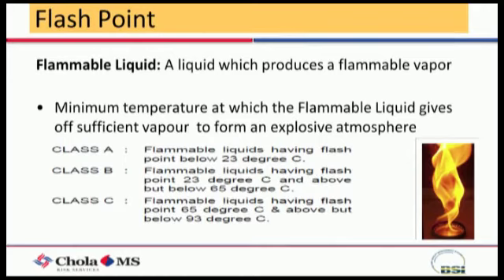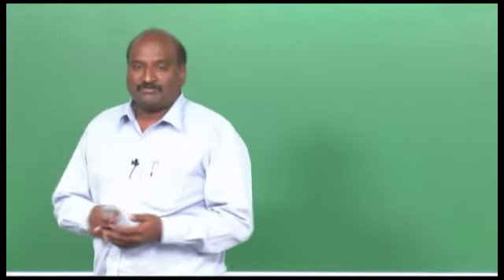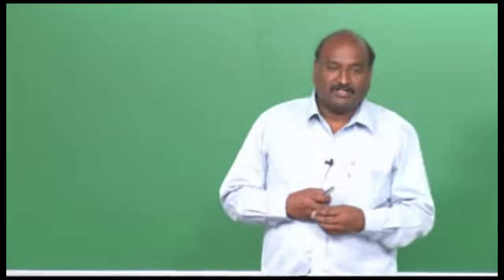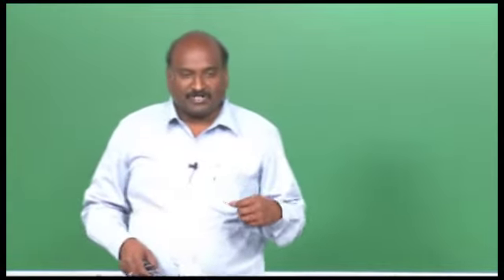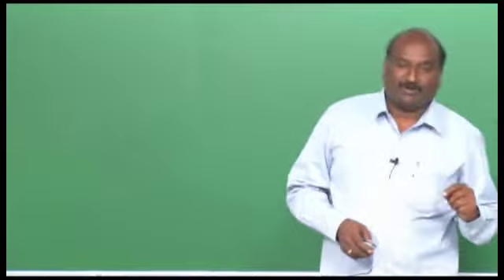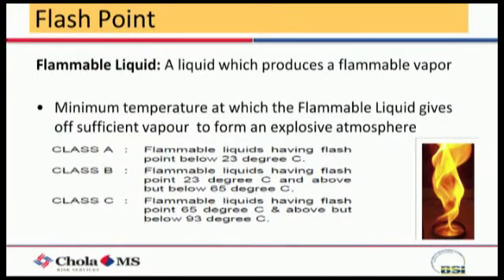Flash point and flammable liquid: a flammable liquid is a liquid which can produce flammable vapours. For example, kerosene or petrol at room temperature — you can feel the vapours or smell them. Class A products have a flash point at 23 degrees, meaning at room temperature they will start giving out vapours. Class B is in the range of 23 to 65 degrees, and Class C is beyond 65 to 93 degrees. This is what is called flammable liquid and flash point.